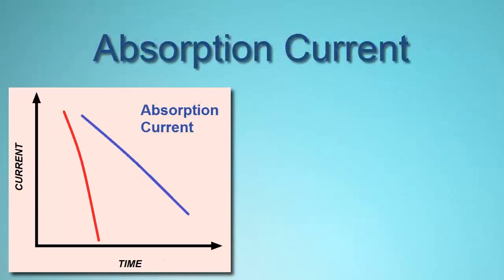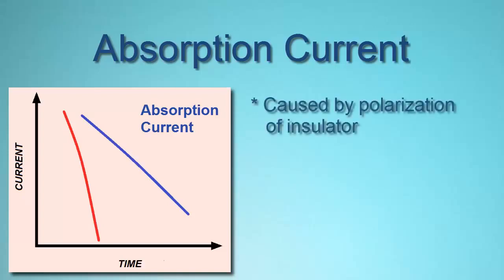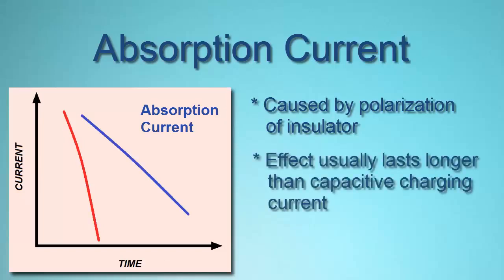Absorption current, also called polarization absorption current, is caused by the insulating material becoming polarized by the electricity flowing through the conductor. As the polarization level increases, the absorption current decreases. This gradual change reflects the storage of potential energy in and along the insulation. As a result, resistance is initially lower and then rises. This produces a measurement profile similar to capacitive charging current, but at a much lower rate. The effect can last several seconds, up to a minute or more.